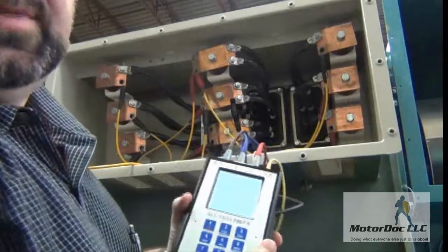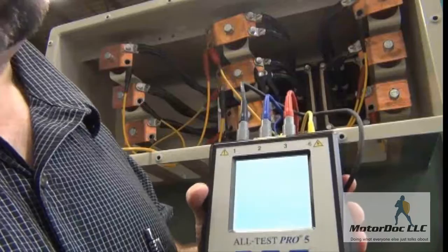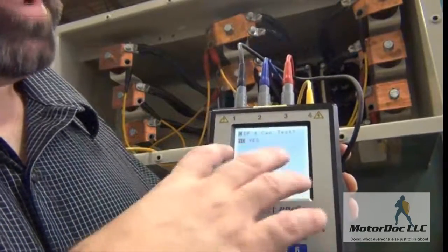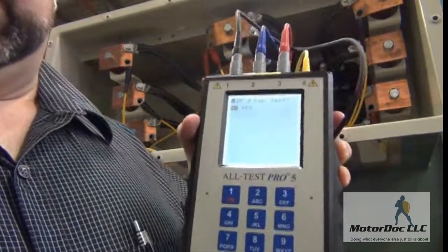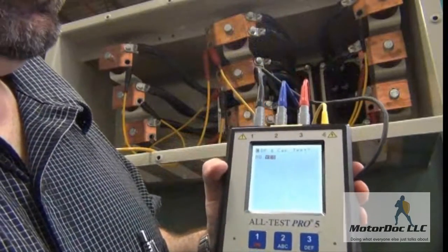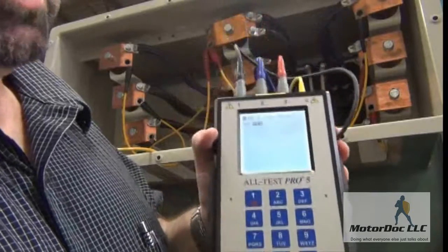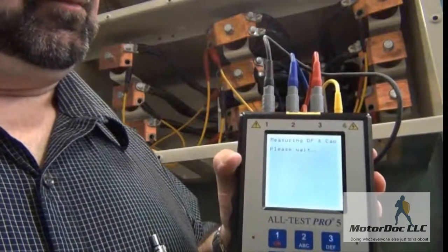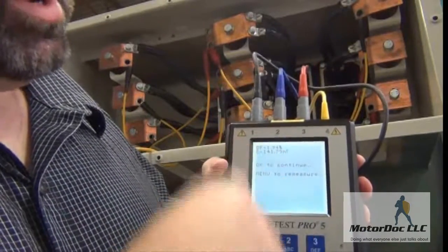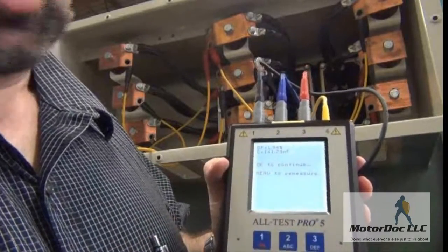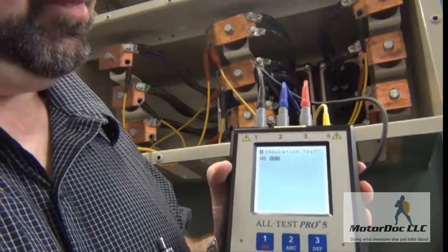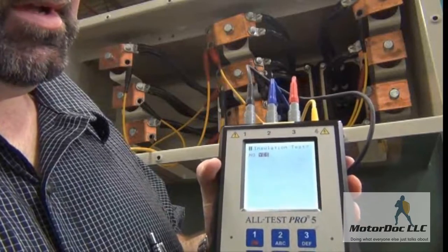Good news — as part of this, it will also check to make sure I have a good connection. I press OK. It's going to ask if I want to do a dissipation factor and capacitance to ground test. Dissipation factor and capacitance to ground tests are covered in another presentation. I select yes and click OK, and allow it to run those tests.